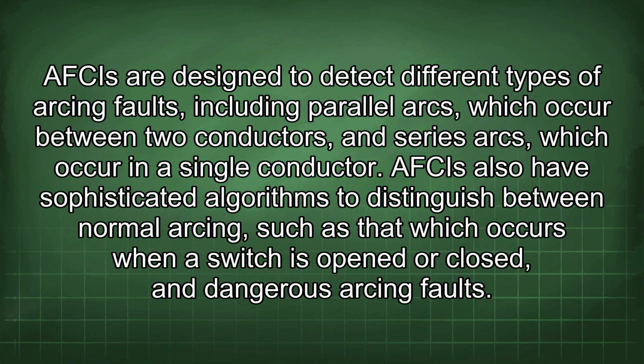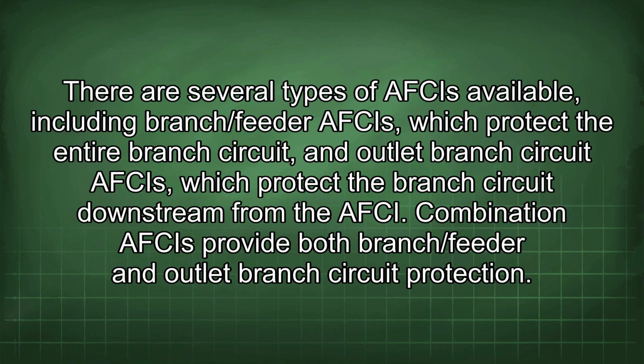AFCIs are designed to detect different types of arcing faults, including parallel arcs, which occur between two conductors, and series arcs, which occur in a single conductor. AFCIs also have sophisticated algorithms to distinguish between normal arcing, such as that which occurs when a switch is opened or closed, and dangerous arcing faults. There are several types of AFCIs available, including branch/feeder AFCIs, which protect the entire branch circuit, and outlet branch circuit AFCIs, which protect the branch circuit downstream from the AFCI. Combination AFCIs provide both branch/feeder and outlet branch circuit protection.